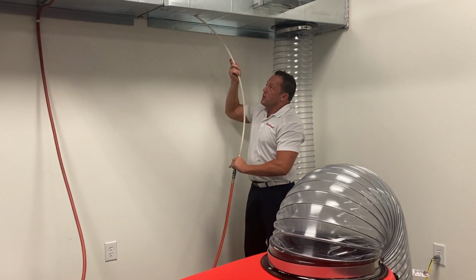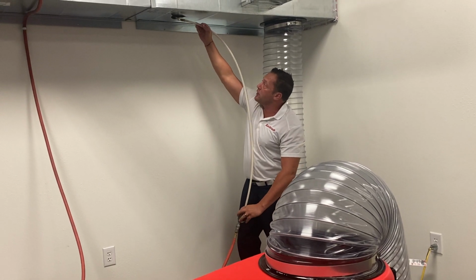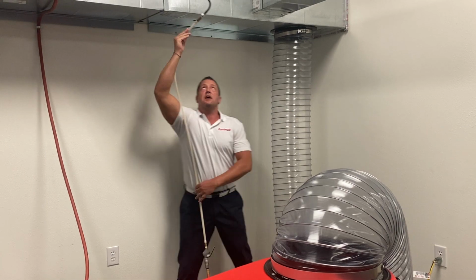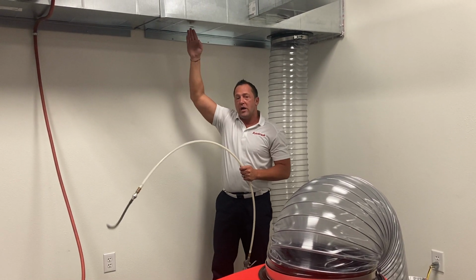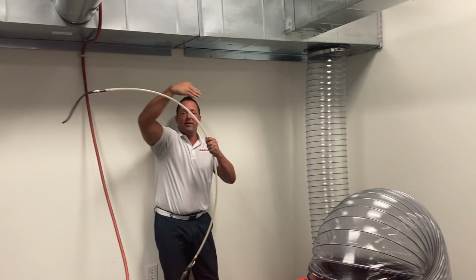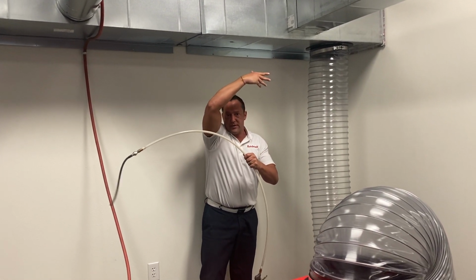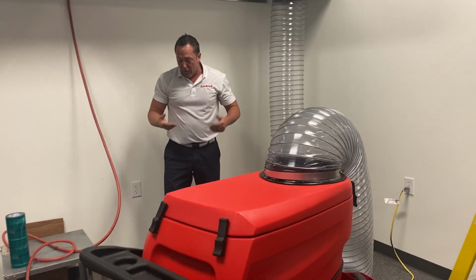Now, this time, with the forward air sweep, I would be pushing the air this way. So in this specific instance, I would either need to turn around and blow back this way. But if I have this 1-inch hole cut here, this would be a great opportunity to put the reverse air sweep on there and send it through, because again, it'd be blowing the air back towards the access hole that I've cut this way.